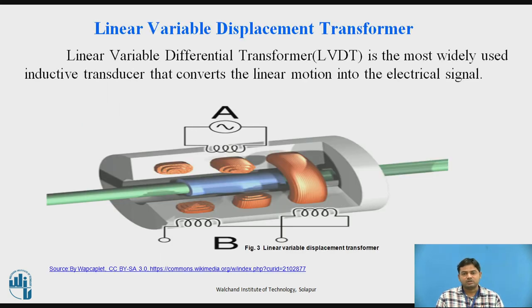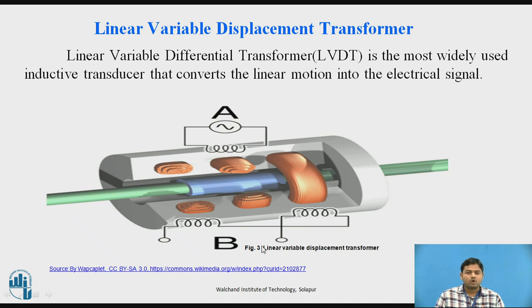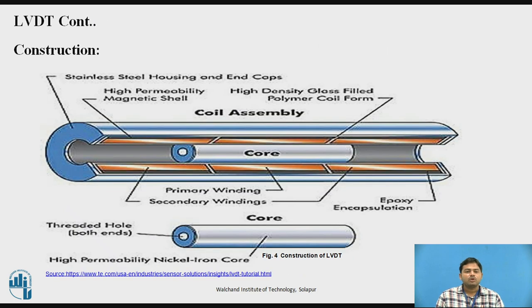Next is the Linear Variable Differential Transducer, also called LVDT. It is a type of transducer that converts linear displacement into an equivalent electrical output — that is, voltage. The conceptual image of the LVDT shows one primary coil and two secondary coils. The main source is connected to the primary coil and the output signal is detected at the secondary coils. There are three coils in the Linear Variable Differential Transducer.